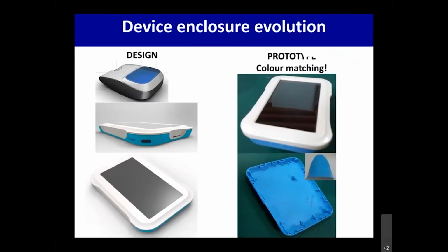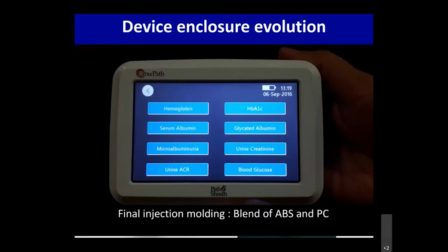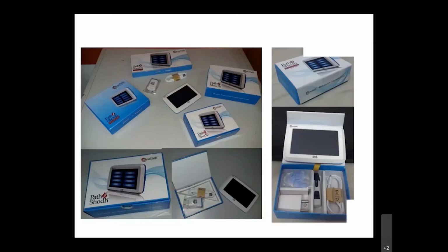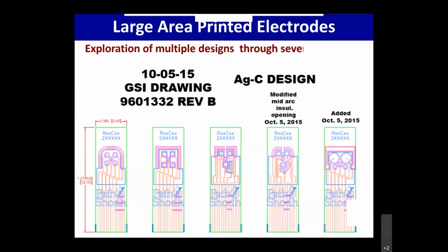So this is the device now which is able to do, as I said, 5 blood tests and 3 urine tests on a single device. And as I said, it's based on test strips. Making this test strip is also very, very challenging, right? I talked about science, but now you need to talk about manufacturing, right? So how do you manufacture them, right? Just like chip manufacturing, you need to manufacture them at very, very large scale. These are all printed, screen printed electrodes, right?